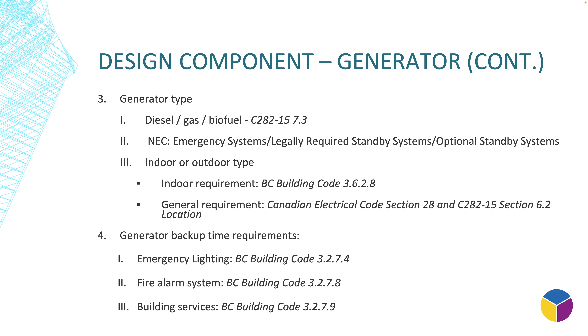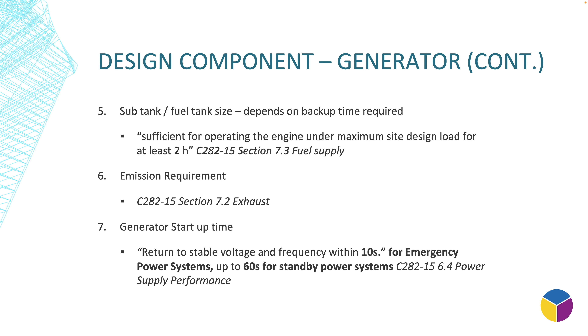For fire alarm, the requirements are different. Normally fire alarm systems are equipped with batteries, and this battery needs to be sized so the fire alarm system stays on standby for at least 24 hours, plus the time it's running. For a high-rise building that would be 24 hours standby plus 2 hours operating at full load. Standby status consumes much less power, while activated status consumes much more power for all the horns.